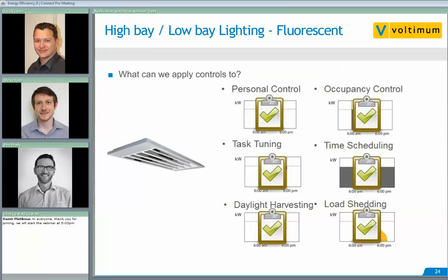Task tuning, load shedding and daylight harvesting can all be bundled into a dimming scenario for fluorescent. We can apply 1-to-10, DALI, or DSI dimming, top-end trim, and step or corridor control. There's a lot of flexibility, and time scheduling is also available — making fluorescent a very good light source for high bay applications.